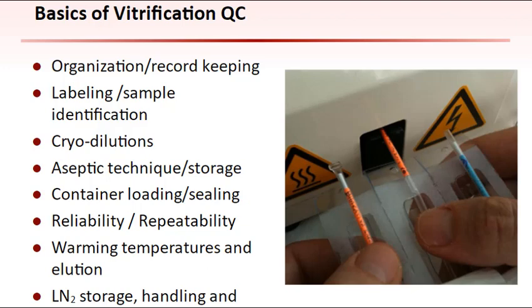Aseptic technique and possible aseptic storage: although viral cross-contamination between embryonic samples in liquid nitrogen storage has never been reported, potential long-term exposure to various contaminants in cryostorage justifies the development and use of aseptic closed devices if their effectiveness can be validated. Container sealing: variation among technicians can depend on the type of sealer used, whether training is required, and the plastic composition and diameter of the straw. CBS straws have a polymer resin that welds together, not by heat, with an automated sealer that eliminates technical variation.